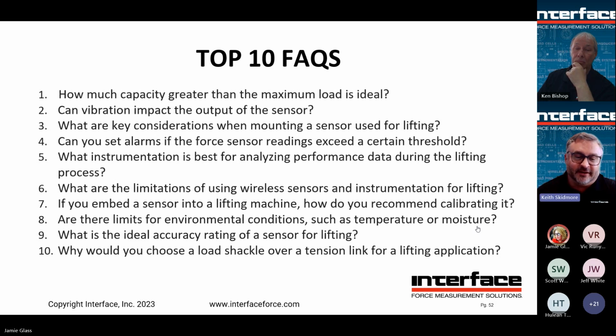What is the ideal accuracy rating of a sensor for lifting? It depends. In a lot of lifting, super precise accuracy is maybe not as important. If you're weighing something in a lift, it might be. Or if you're handling something extremely critical and fitting pieces together, you don't want to press them together, or allow the weight of the system to press the parts together, with too much force, so it might be extremely important to measure accurately. It really depends on the application. But for lifting and rigging, accuracy usually isn't the driving factor. It's more monitoring and making sure things are being done safely.